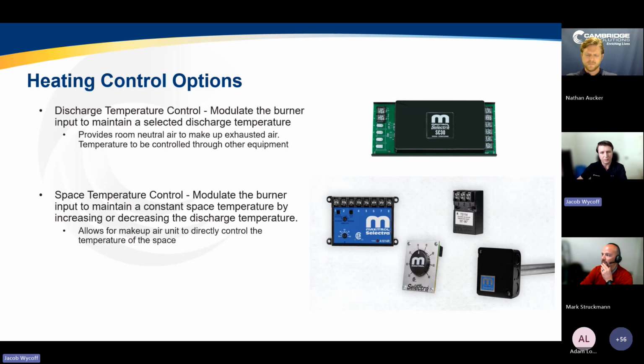Sometimes you're going to be controlling the temperature of the space through other equipment, or oftentimes discharge temperature control units will have a routine that if the space temperature drops too low, it'll increase the discharge temperature by a set amount. The other option is space temperature control, where you modulate the burner to maintain a constant space temperature by increasing or decreasing the discharge temperature within a range. This is great because it allows the makeup air unit to directly control the temperature of the space and is a great option whenever you want tighter control over the temperature within the space.